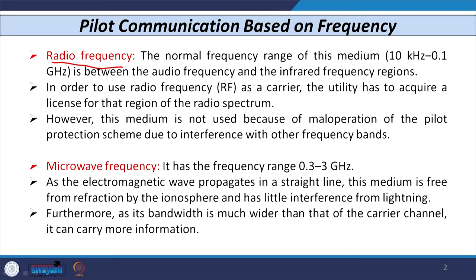When we use radio frequency, the normal frequency range is from 10 kilohertz to 0.1 gigahertz. When we use such a scheme, the utility has to acquire a separate license and a separate band for that frequency range for transmission of signal. However, this type of medium is not used because of mal-operation of the pilot relay due to interference with some other frequency band.